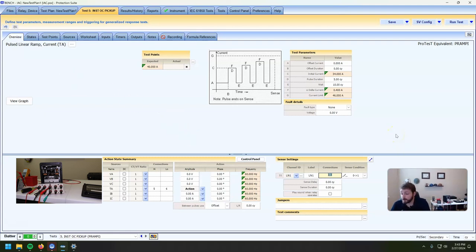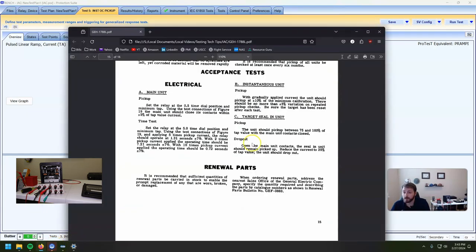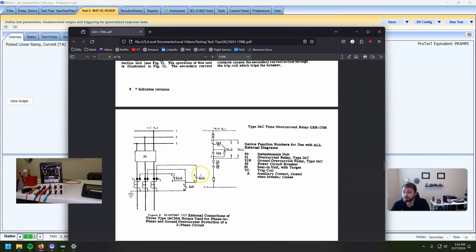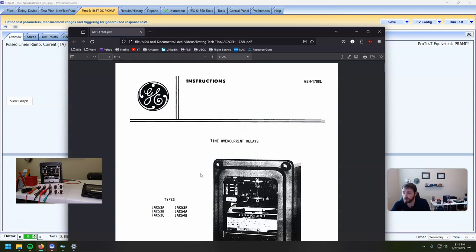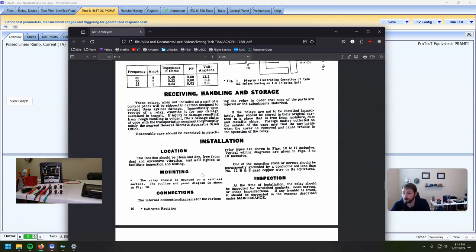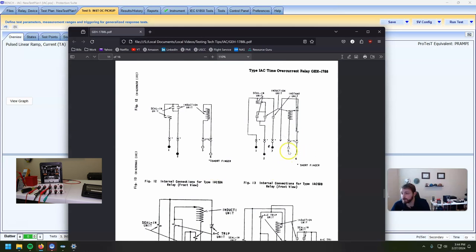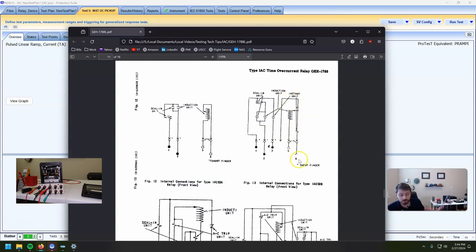That worked great. If our impedance was too high — it'll vary relay to relay, setting to setting, and test set to test set — on this one, if impedance from five to six was too high and the test set was having a hard time pushing 40 amps to get it to trip, we would have been able to connect to terminal four on our test paddle, go four to six, and that would have picked up our instantaneous unit with a little bit less impedance. That's why that's there — just keep that in mind.